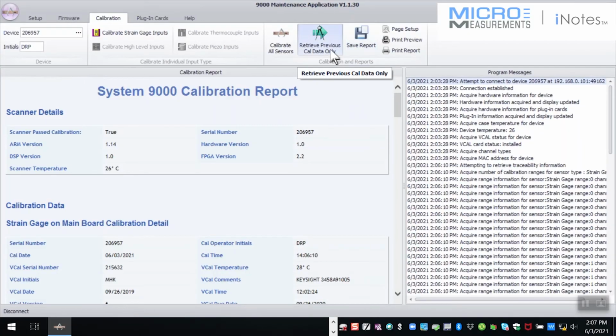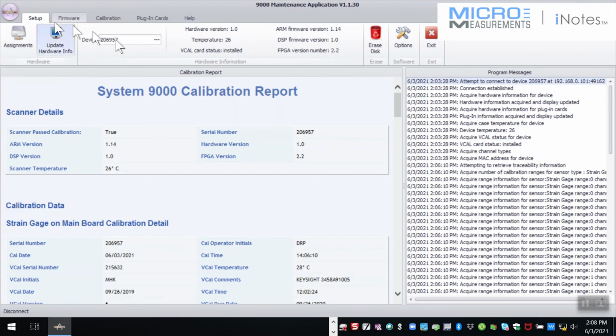And we have the opportunity to both retrieve previous calibration reports that were performed and save the one that we just did in any different format. So you've got lots of convenient options to document that you do have traceability with the scanner. So again, the system calibration and the firmware updates are conveniently here in what we call the maintenance utility or the maintenance application. But the primary thing that you needed to do was to create this assignment, make sure that connectivity was there. And really, that's the fundamental, that's it. The rule, if you will.